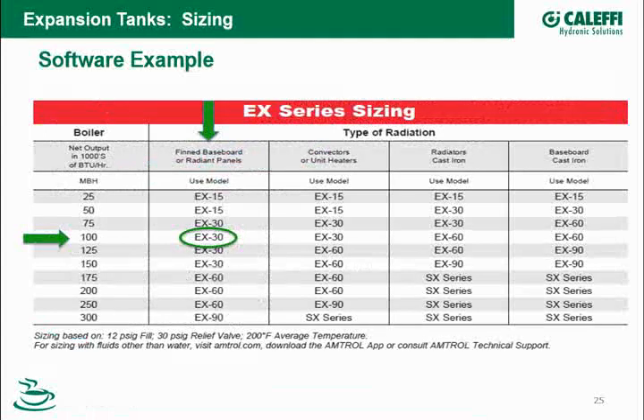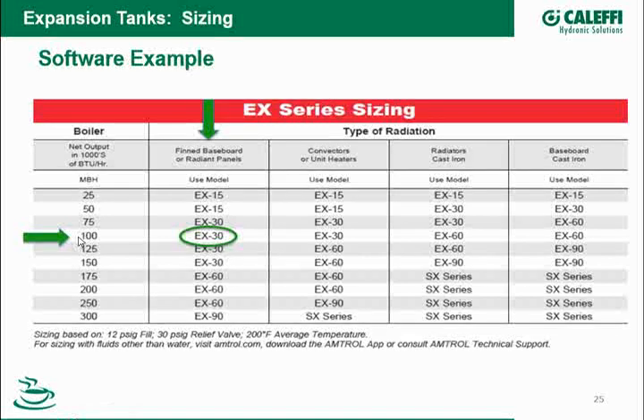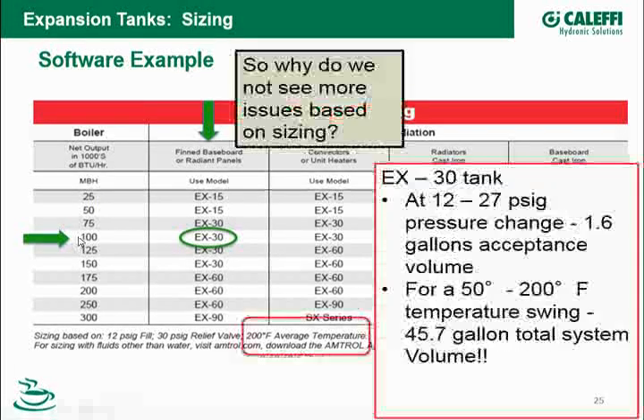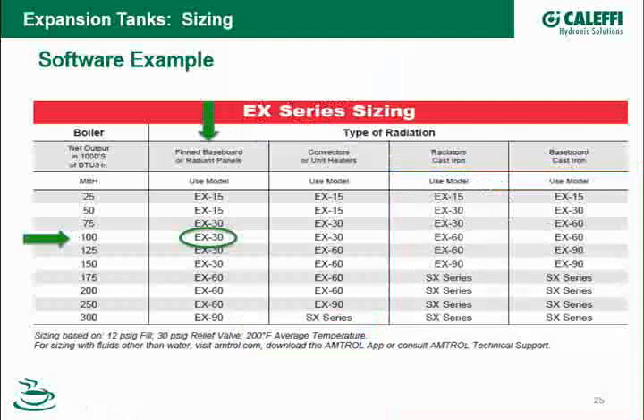Okay, this is an example of a chart which most of the manufacturers have. That's a quick sizing method. You enter it on the vertical column with the type of radiation, and then you go with the net output on the boiler. So, for instance, if I'm doing baseboard radiation and I have a boiler that has a net output of 100,000 BTUs, I want to do a Model 30 expansion tank. This is based on incoming pressure of 12 psi, a 30-pound relief valve, and a 200-degree average water temperature.